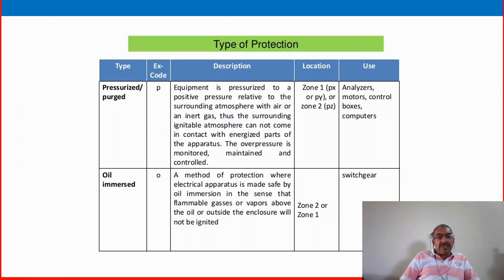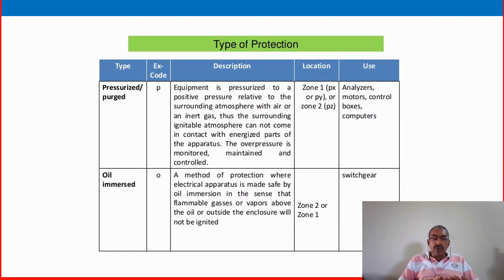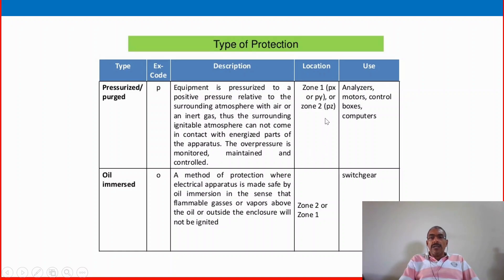Type of protection — pressurized or purged gas, code P: equipment is pressurized to a positive pressure relative to the surrounding atmosphere with air or an inert gas, so that the surrounding ignitable atmosphere cannot come in contact with energized parts of the apparatus. The overpressure is maintained and controlled, usually using a blanket gas — for example, inside a storage tank, equipment is always pressurized to maintain positive pressure. If the pressure drops below atmospheric pressure, air and oxygen mix with hydrocarbon gas creating a hazardous situation.